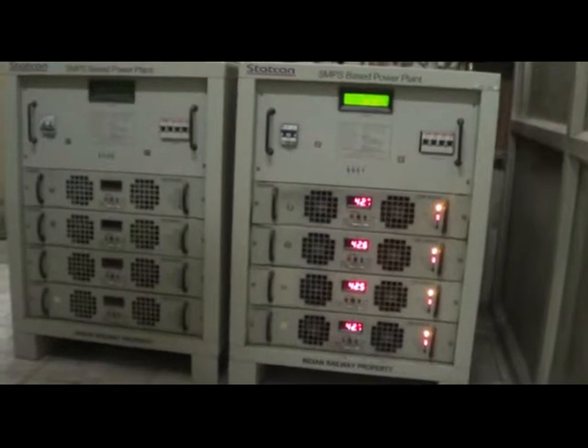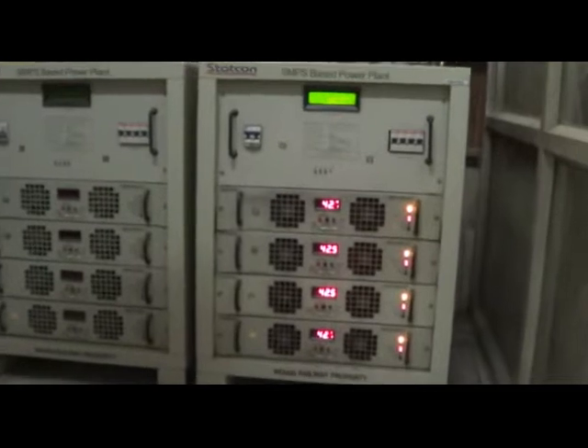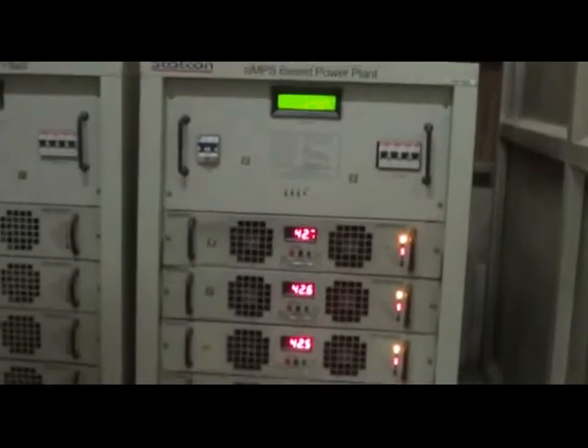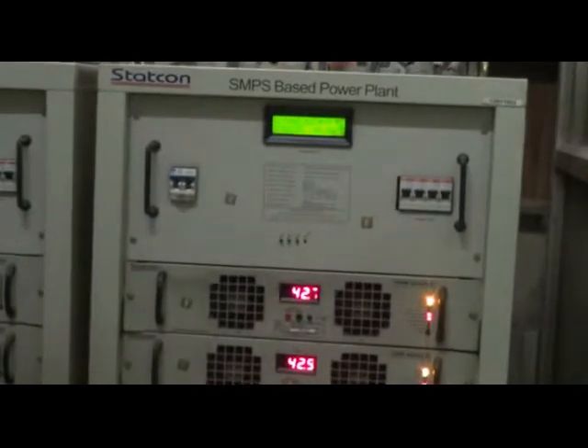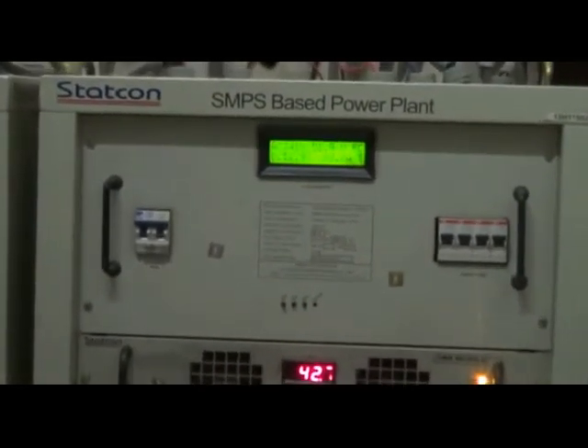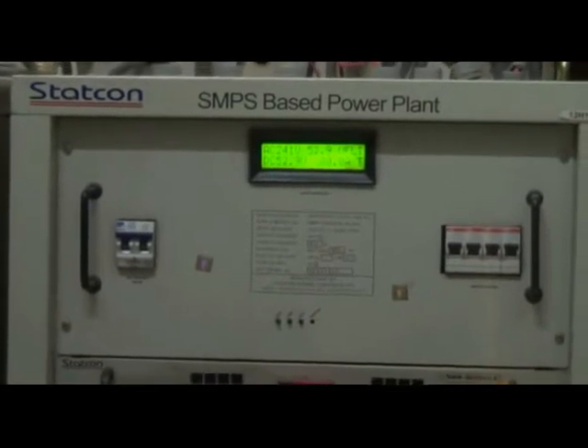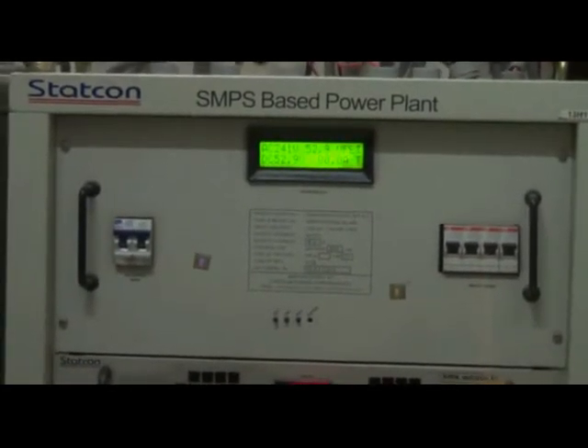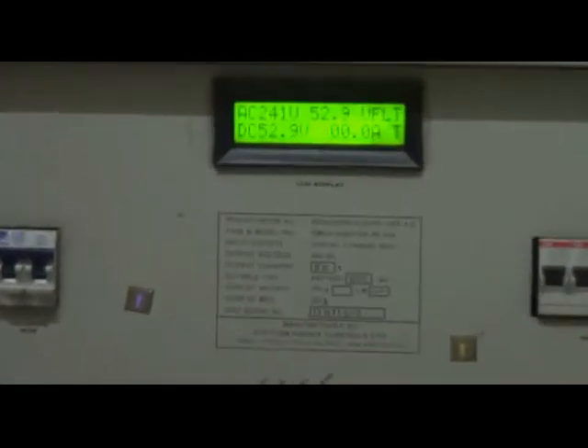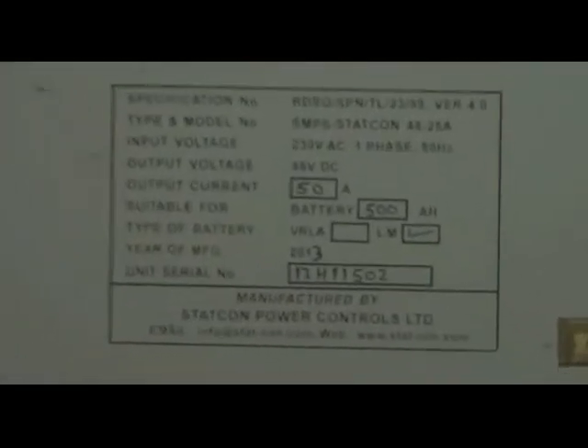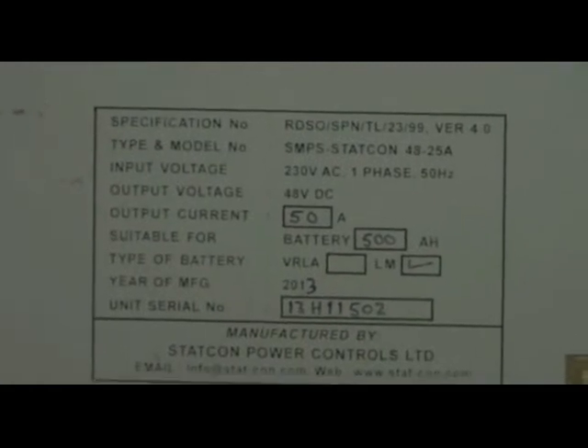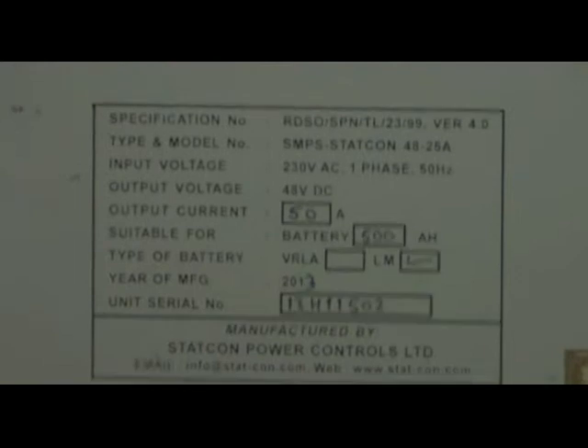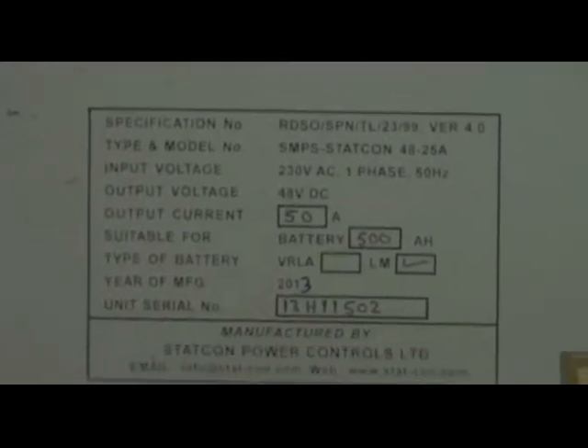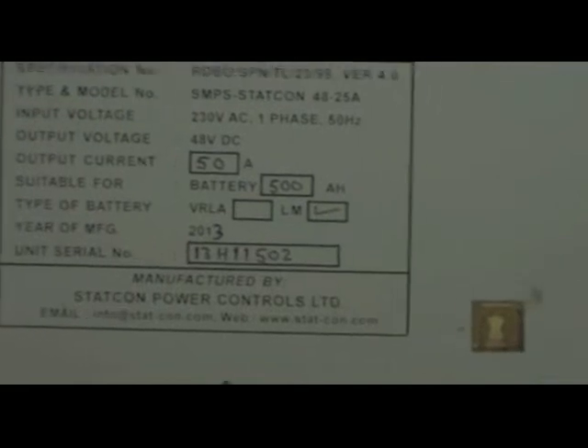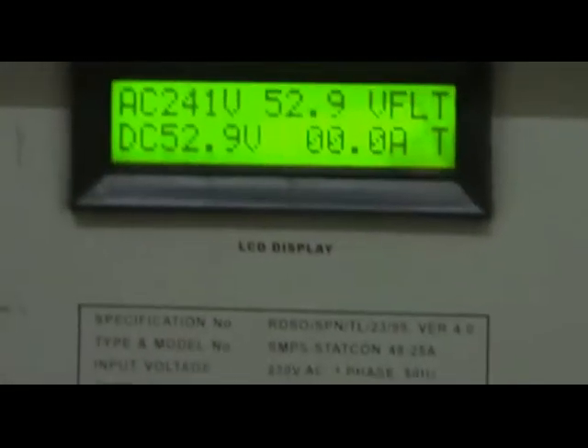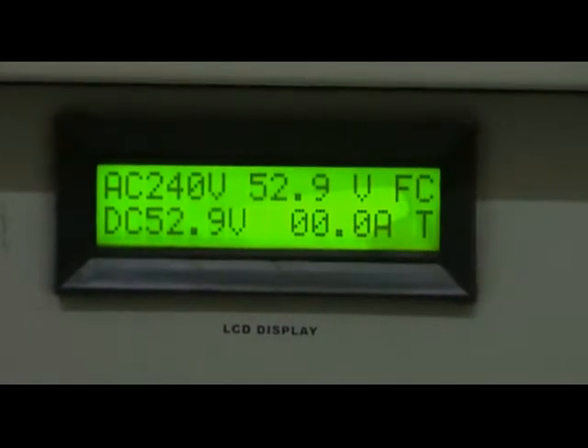This short video film covers the technical requirements of 48 volts DC power plant manufactured by STATCON Power Controls Limited, based on high frequency switch mode techniques for the use by Indian Railways for telecom installations such as telephone exchanges, multiplexing equipments, microwave radio equipments, GSMR equipments, Tetra equipments, OFC equipments, etc. This power plant will work either with valve-regulated lead acid or conventional lead acid batteries.